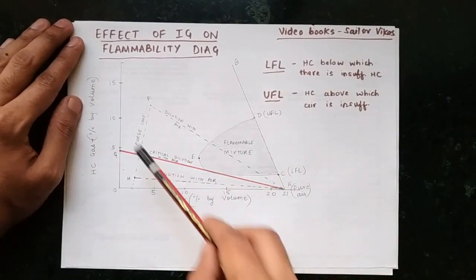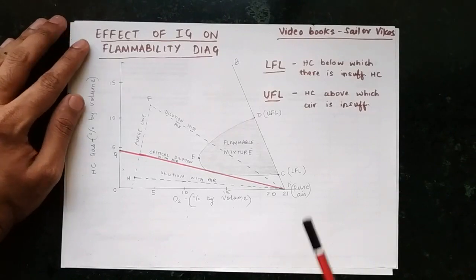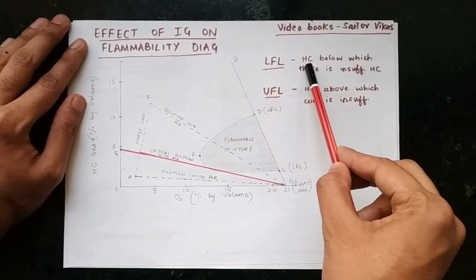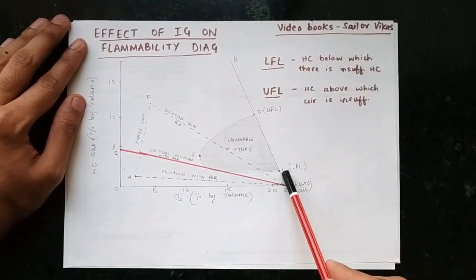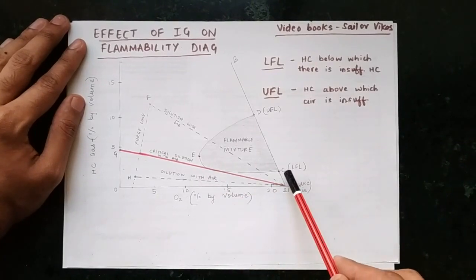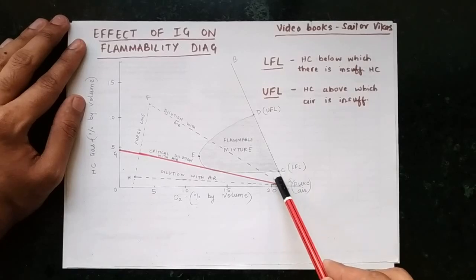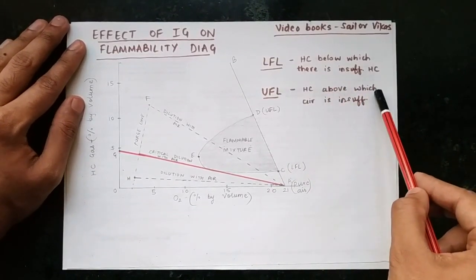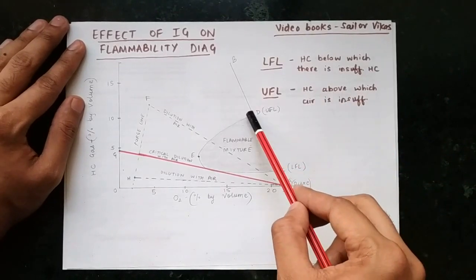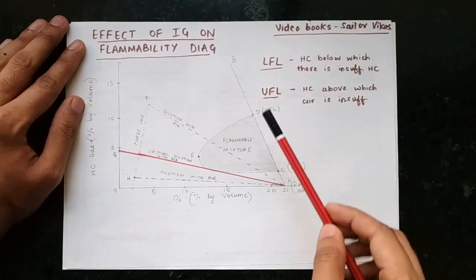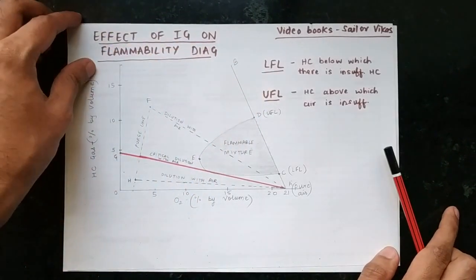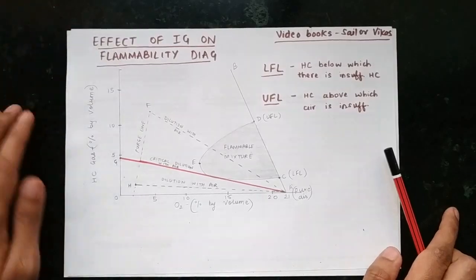LFL is the hydrocarbon concentration below which there is insufficient hydrocarbon for combustion — if the hydrocarbon is less than this point, it will not be combustible. UFL is the hydrocarbon concentration above which there is insufficient air for combustion to occur. LFL can also be termed as LEL — lower explosive limit — and UFL can also be termed as UEL — upper explosive limit. Both are the same.